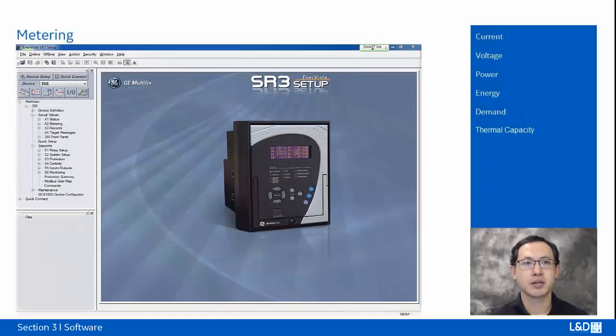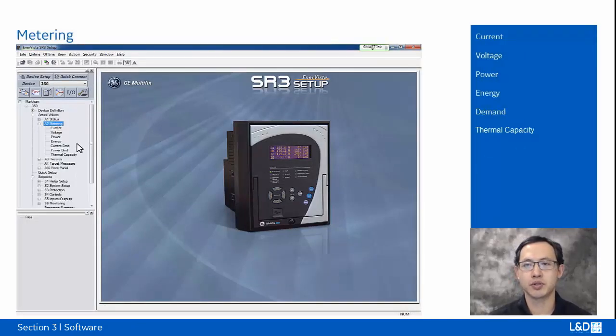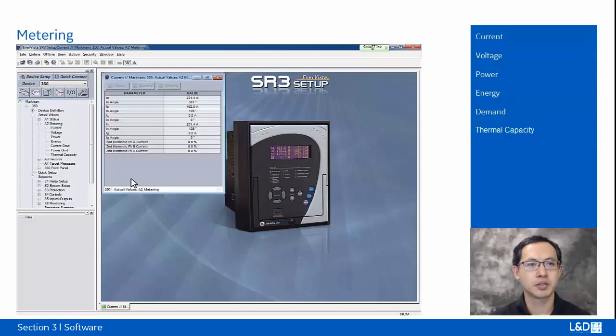Metering is under the Actual Values A2 metering. Double click A2 metering. We can see the metering for the current, voltage, power, energy, demand, and thermal capacity. So if we open the current, we can see the 3-phase current for this application.